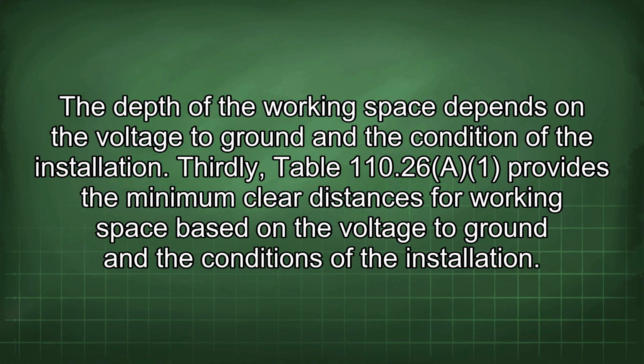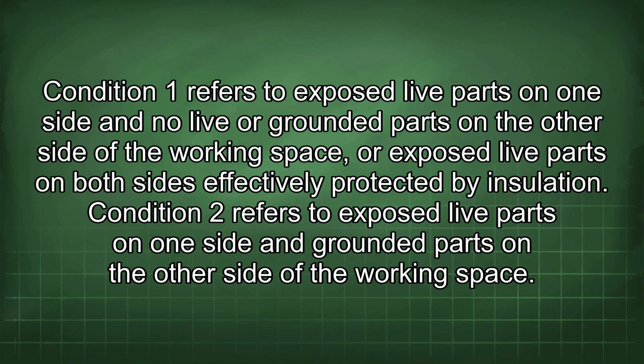Thirdly, Table 110.26(A)(1) provides the minimum clear distances for working space based on the voltage to ground and the conditions of the installation. Condition 1 refers to exposed live parts on one side and no live or grounded parts on the other side of the working space, or exposed live parts on both sides effectively protected by insulation.